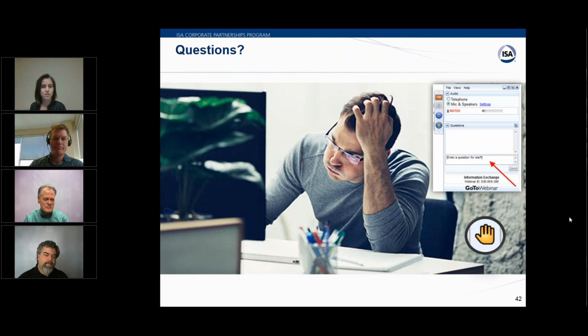Okay. Based on your experience, what would a reasonable calibration frequency be? Well, if you want to be conservative, follow the manufacturer's recommendations. These gentlemen will tell you more. One of the benefits of documenting all of your calibration is that you'll have historical proof that you can make the recommended calibration period longer. I did just that. The manufacturer is conservative. He wants to make sure that he doesn't get blamed if something goes wrong. We had documentation, and we went from 3 months to 5 months calibration frequency on some of our gas detectors, but we had the documentation to prove that the drift was sufficiently low that we could get away with that.